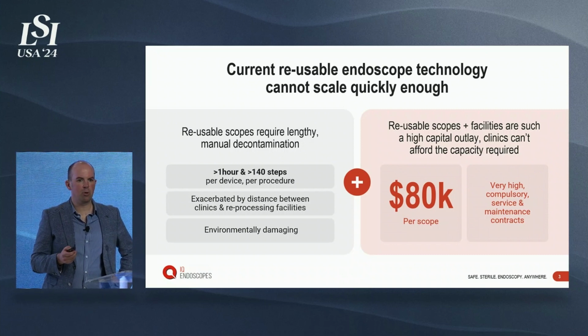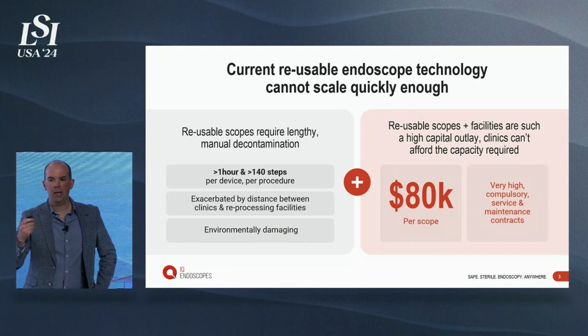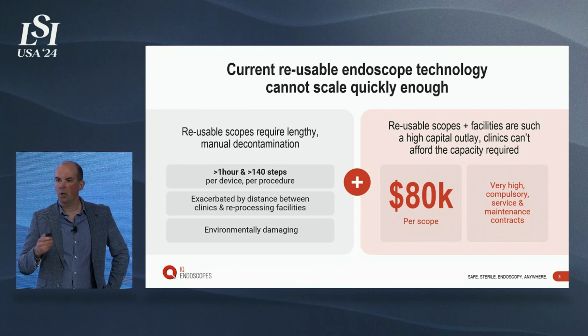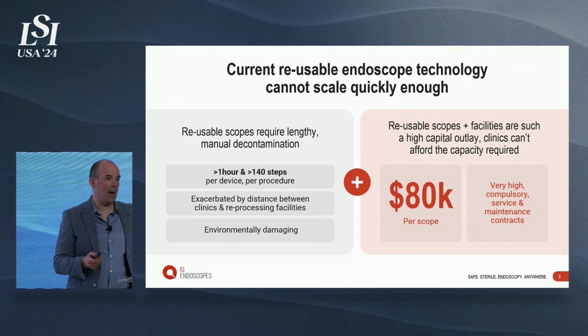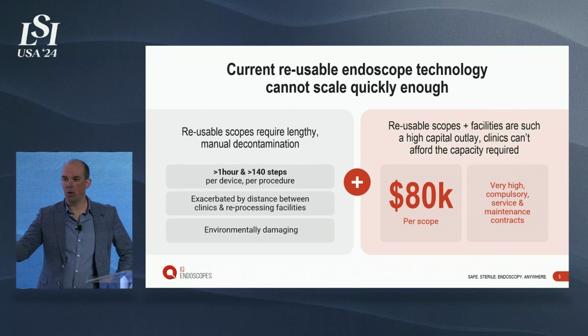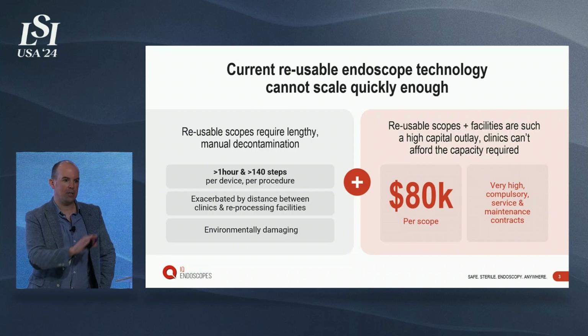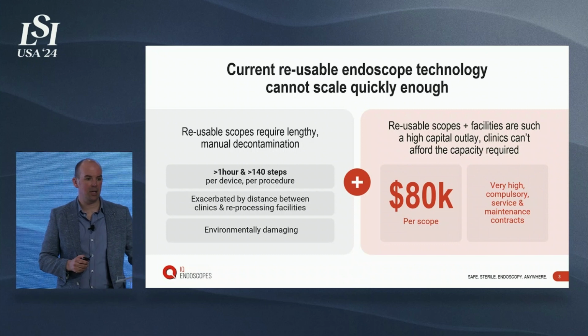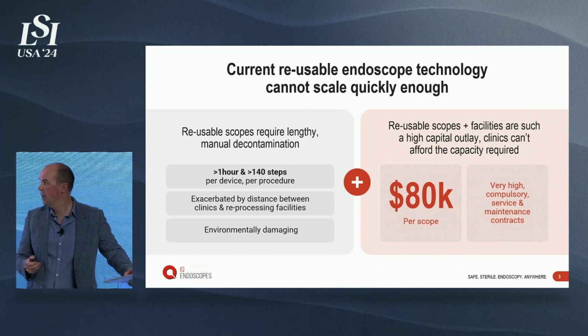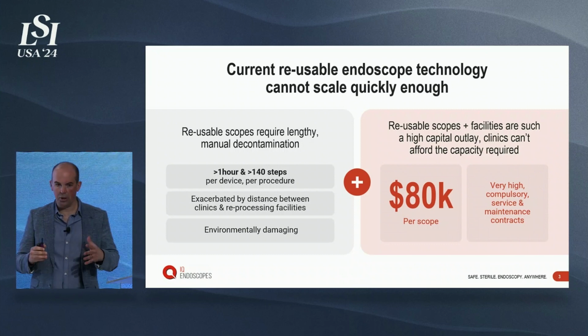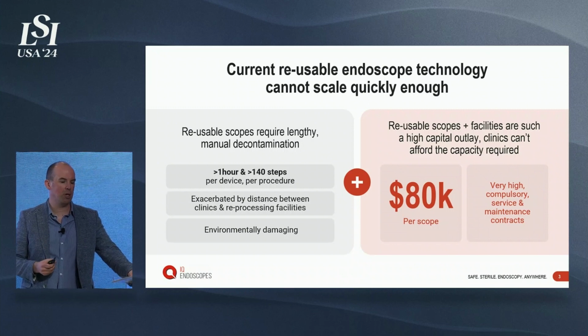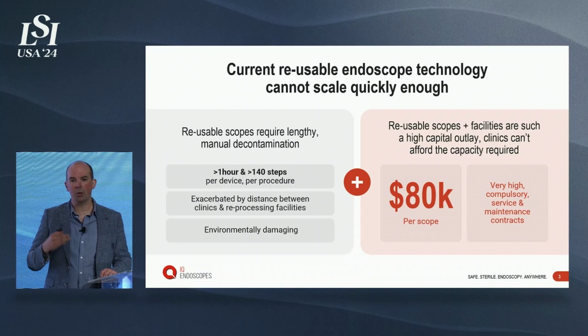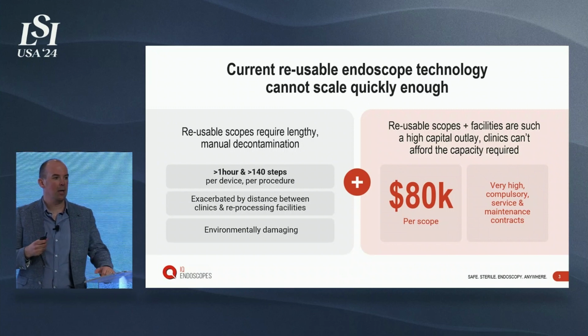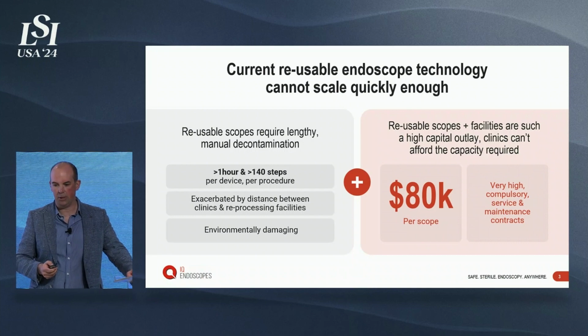Also, the device is reusable. So once it's been used, it gets sent off to decontamination, which is a complex process which takes over an hour, might be on site, might not be on site, and that scope has to come back into circulation in time for that procedure for the next patient. So we're not saying that single use will replace reusable. What we're saying is that reusable cannot cope with the capacity demands that health systems need to carry out endoscopies.